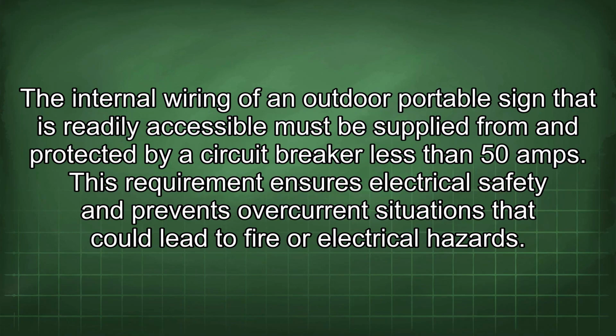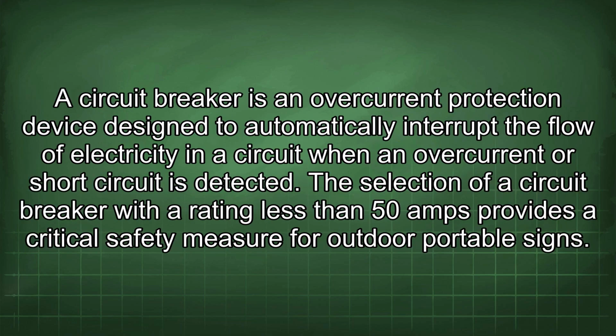The internal wiring of an outdoor portable sign that is readily accessible must be supplied from and protected by a circuit breaker less than 50 amps. This requirement ensures electrical safety and prevents overcurrent situations that could lead to fire or electrical hazards. A circuit breaker is an overcurrent protection device designed to automatically interrupt the flow of electricity in a circuit when an overcurrent or short circuit is detected.